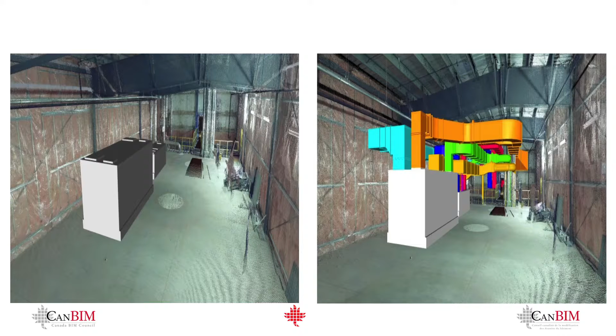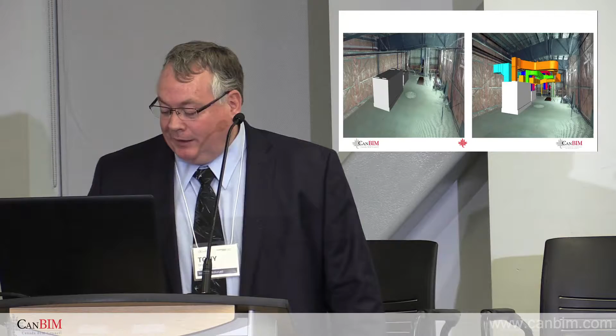So we scanned it, then started to populate the model using the approved shop drawings, then added the ductwork. You can see that the beams on this engineered building are sloping, so because we're working with a scan with all the existing data, we can ensure our ductwork actually fits and where it's going to end up.